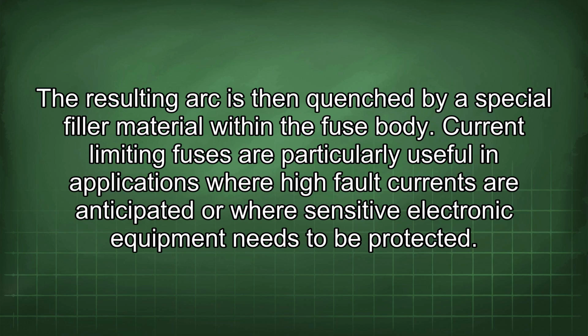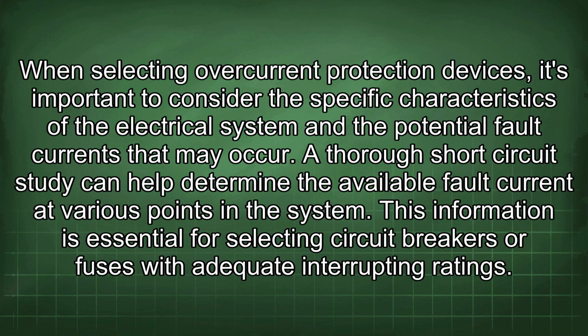Current-limiting fuses are particularly useful in applications where high fault currents are anticipated or where sensitive electronic equipment needs to be protected. When selecting overcurrent protection devices, it's important to consider the specific characteristics of the electrical system and the potential fault currents that may occur. A thorough short-circuit study can help determine the available fault current at various points in the system. This information is essential for selecting circuit breakers or fuses with adequate interrupting ratings.